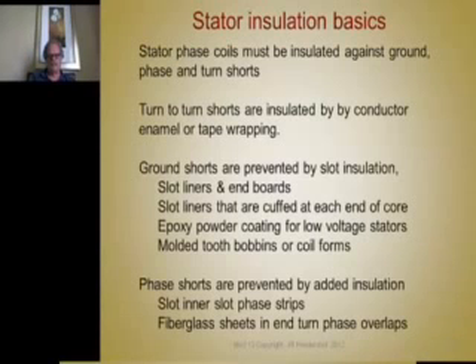Slot liners are frequently cuffed at each end, similar to the cuff of a dress shirt collar, so that the insulator stands up on these cuffs on the ends, which eliminates the need for an end board. As long as the cuffs never get crushed by forming of the end windings, that supports the end winding and keeps them a distance away from the end of the core equal to the height of the cuff.